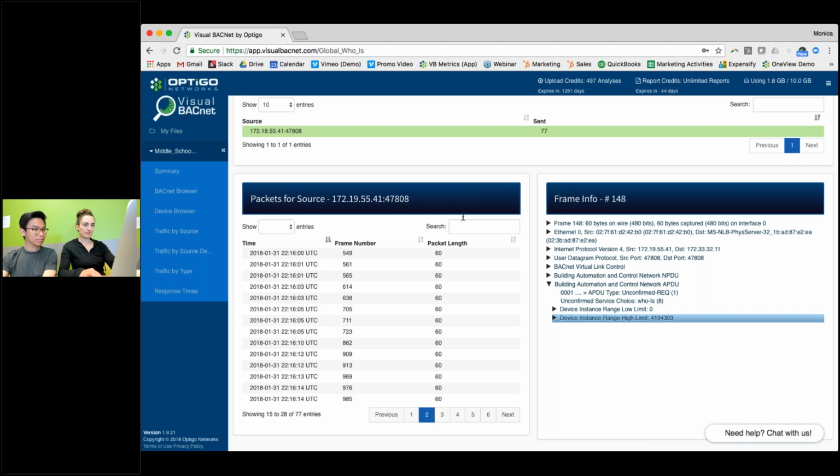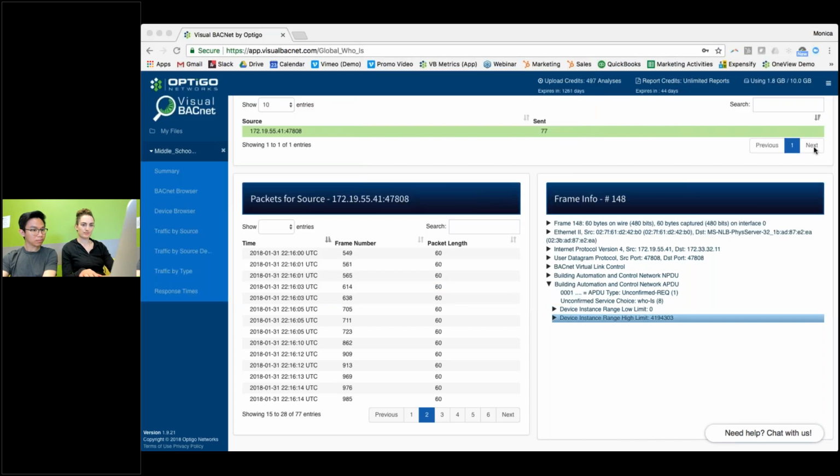So now we're talking about 4.2 million packets, right? That's what it's looking for, and you can potentially get those back. So it's good practice to not do this. You'll see in many other BACnet implementations, in this range, a 0 to 10 or a 0 to 100 and then a 101 to another number. What that's doing is it knows where the controllers are and it's looking for the gaps within to see if something new came. That's a software approach to making sure your list is updated.